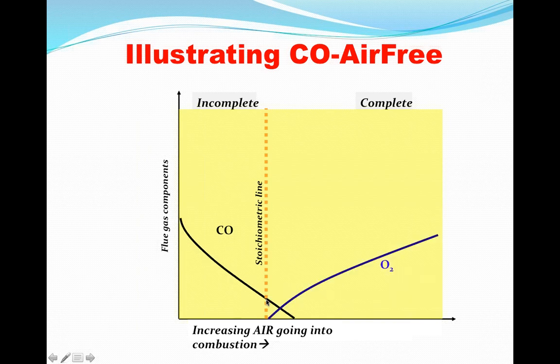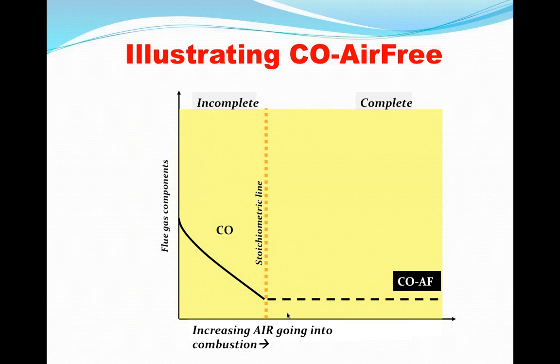I'll go back a couple steps. One of the main reasons that the CO is dropping here is part of it is due to dilution. The concentration gets much less because you're adding excess air to it, you're diluting it. It also drops because there's more air available to reduce the amount produced, but there still could be an amount produced. That amount produced, if you could look back and see where it crosses the threshold, the stoichiometric line, that's what CO-AirFree is. It's the ability to use a microscope and look back, no matter what set point you are at for the oxygen reading, and see your CO-AirFree as one number going back here.